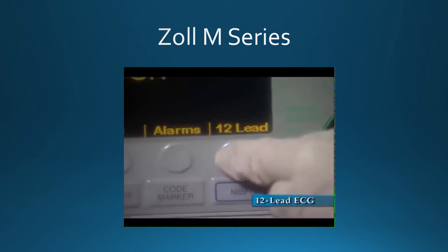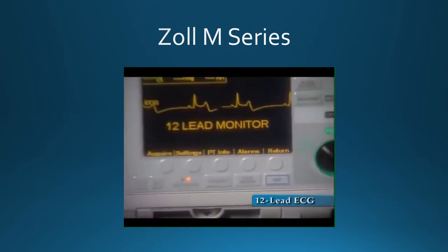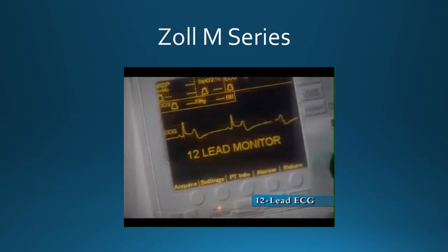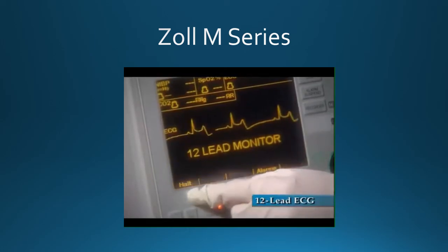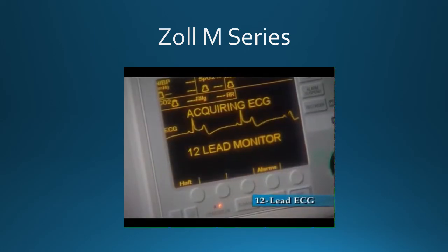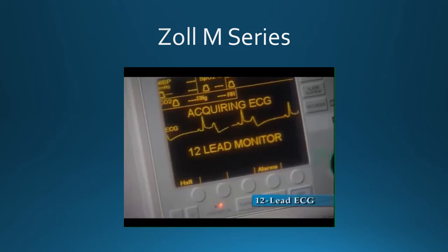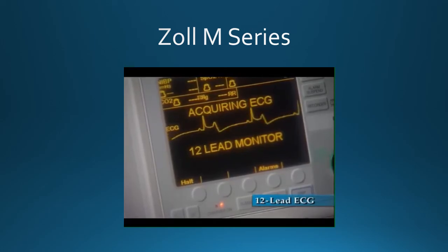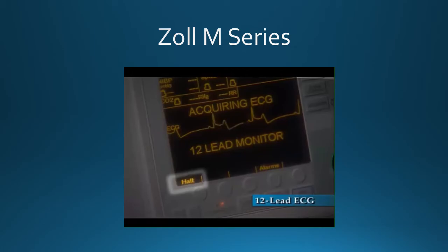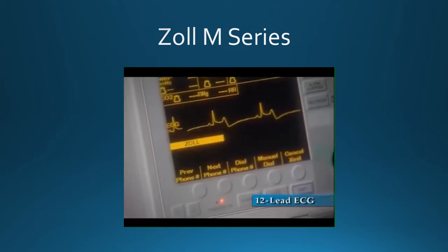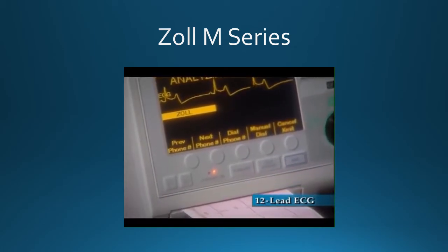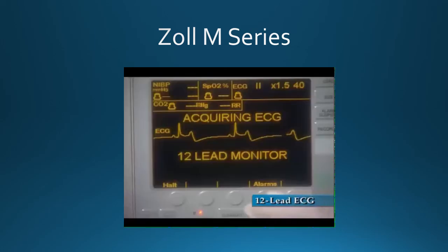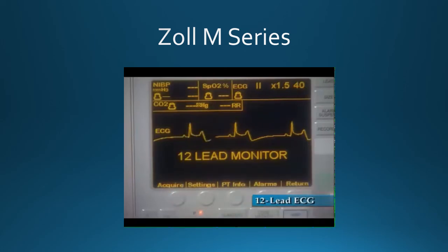When the 12-lead soft key is pressed, the following screen will be displayed. Pressing the Acquire soft key begins the 12-lead acquisition process. The acquiring ECG message will be displayed, and the Acquire soft key changes to Halt. The 12-lead ECG interpretation and measurements will print if so configured. The Halt soft key can be pressed at any time to abort the 12-lead process. When the Halt soft key is pressed, the acquisition halted message is displayed.